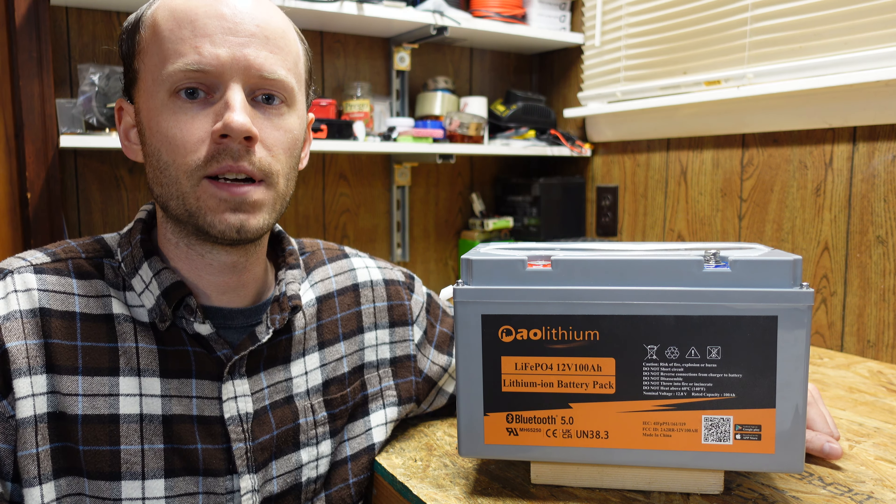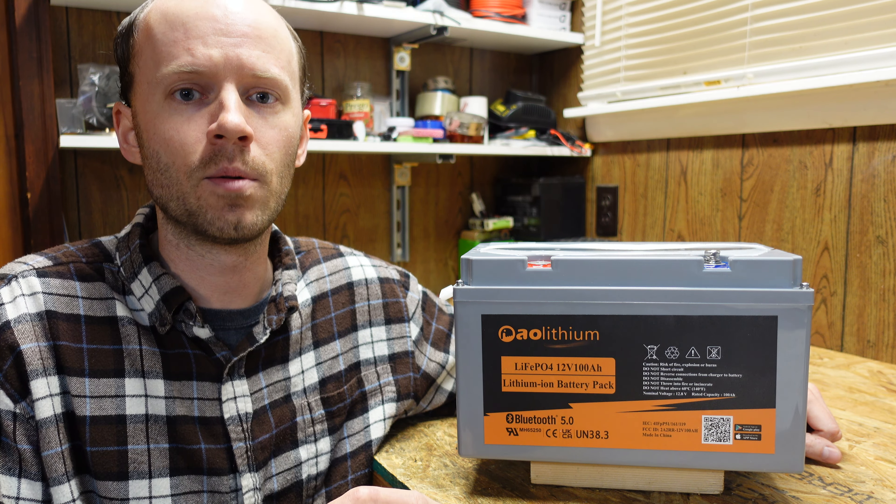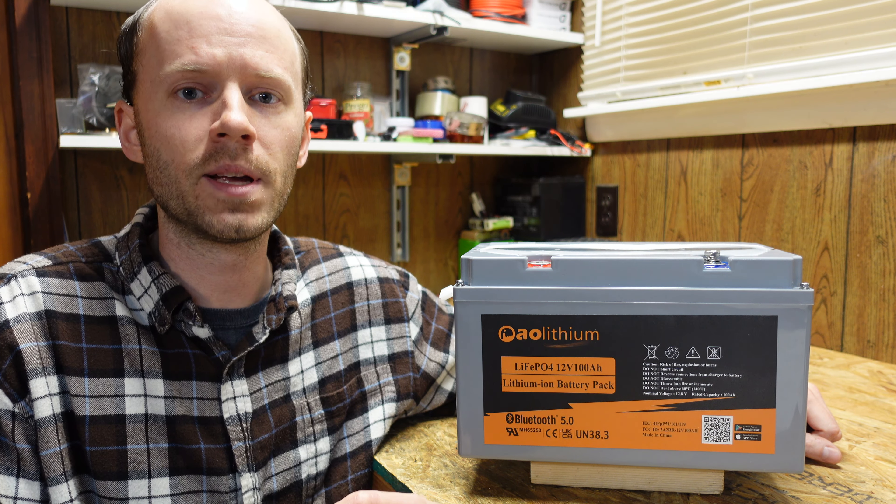When I saw that, I quickly contacted the manufacturer to see what their statement was on this and figure out what exactly was going on. The first thought that came to my mind was that the data sheet I found was version A, and perhaps there was a new version released since then. I finally received a response this morning, and the manufacturer has issued a statement and an apology that the rating of this battery is only 100 amps continuous discharge.